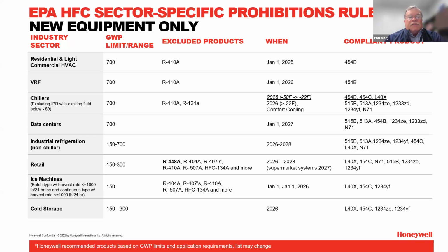The point I'd like to make on this slide is you've got pretty hard reductions in GWP. A lot of the existing products are going away in 1, 2, or 3 years. There are substitutes on the far right. For really every application the industry has developed - and it's not just Honeywell, there are others - making things that mimic performance, such as the 454B and the 32, pretty much with your gauge sets and the rest of it looks like 410A, and all through refrigeration, the same thing.